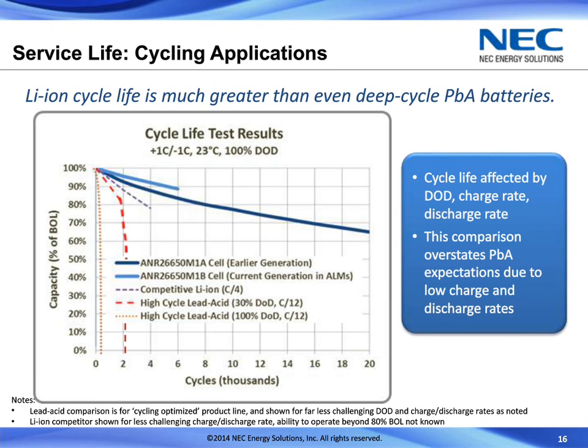The other factor here is that cycle life is really dependent on and affected by how deep you discharge the battery for each cycle, and also the rate at which you charge and discharge. The deeper you go, or the faster you charge and discharge, the more quickly the battery will wear out, especially for lead acid. In this example, it's not really a fair comparison between these various devices.